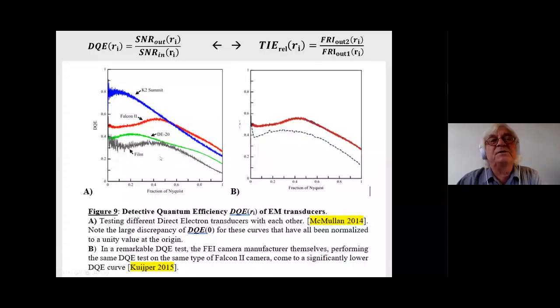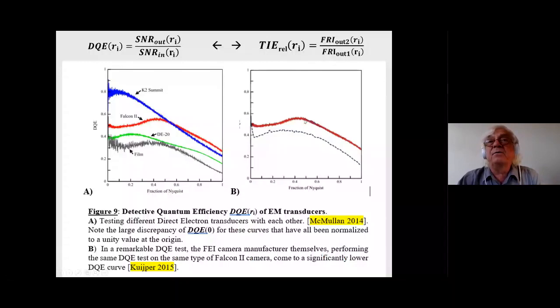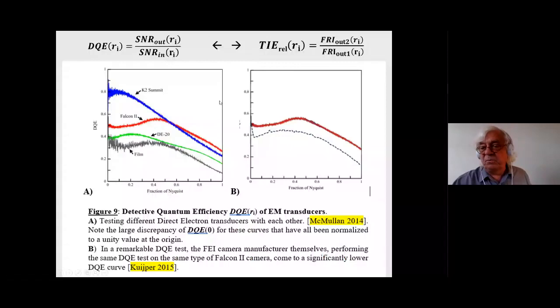The interesting thing is that the DQE measurement done by Richard Henderson's group at MRC and the same thing done by FEI themselves on the same camera type disagree — FEI found their camera is worse than suggested. But the problem is not whether the camera is better or worse — the metric is not good. So all the X-ray equipment we get subjected to is based on this kind of flawed definition.